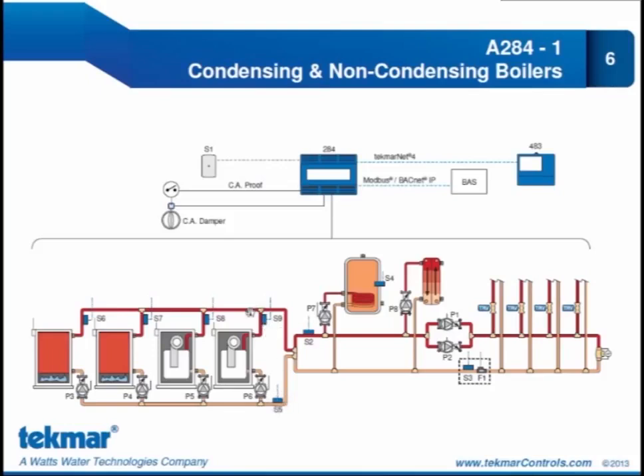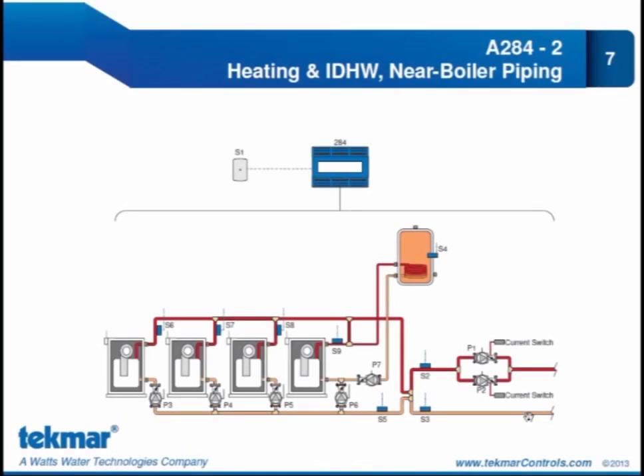Because I have the inlet sensor and the outlet sensor for every boiler, I can also do a delta T measurement across every boiler. And that is also information that can be communicated to the building automation system. Our second application shows 4 modulating boilers that are being operated to provide space heating and indirect domestic hot water. You can see that the 4th boiler is solely responsible for the indirect domestic hot water generation.